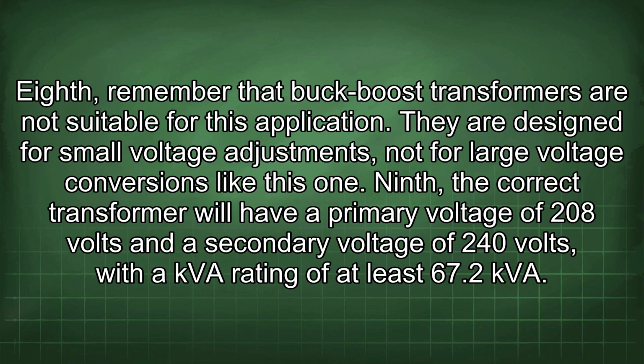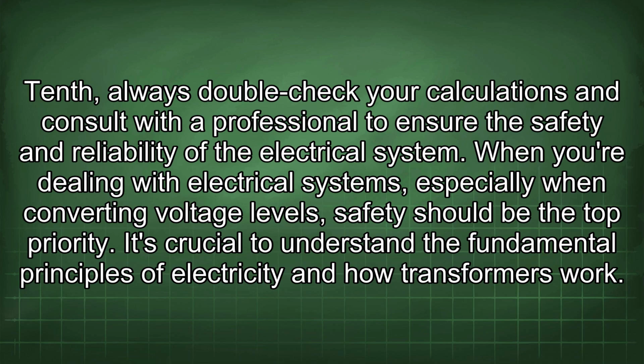Eighth, remember that buck-boost transformers are not suitable for this application. They are designed for small voltage adjustments, not for large voltage conversions like this one. Ninth, the correct transformer will have a primary voltage of 208 volts and a secondary voltage of 240 volts, with a kVA rating of at least 67.2 kVA. Tenth, always double-check your calculations and consult with a professional to ensure the safety and reliability of the electrical system.